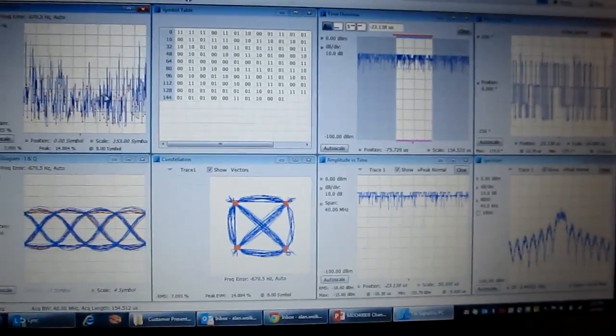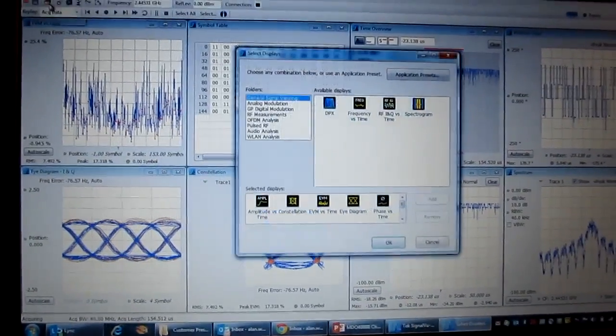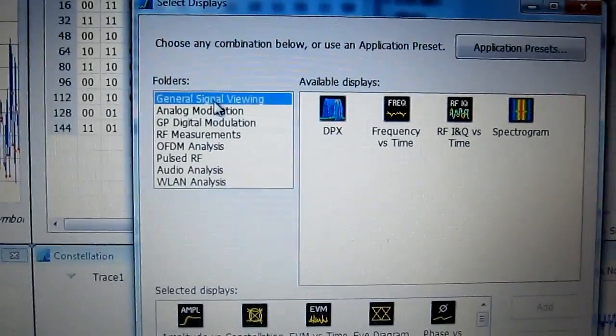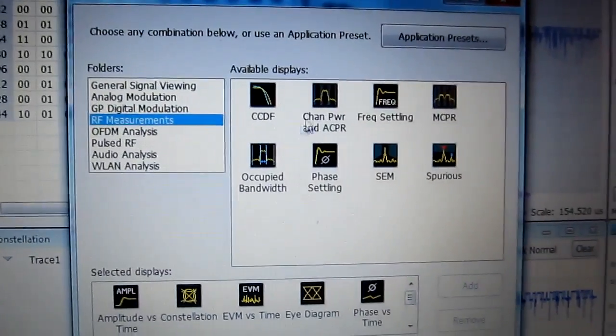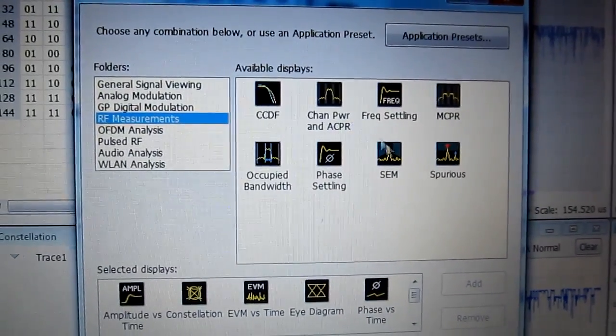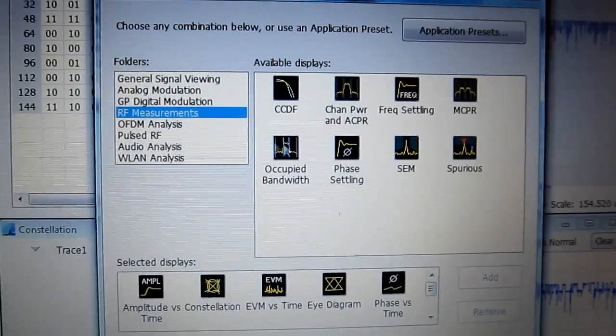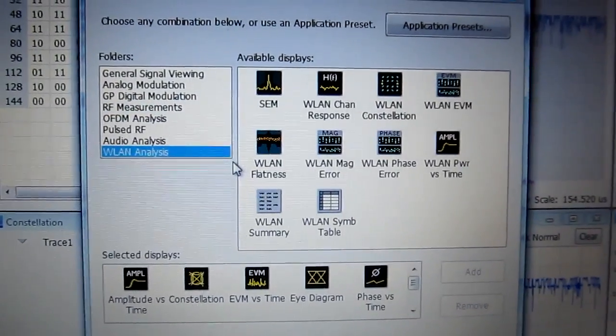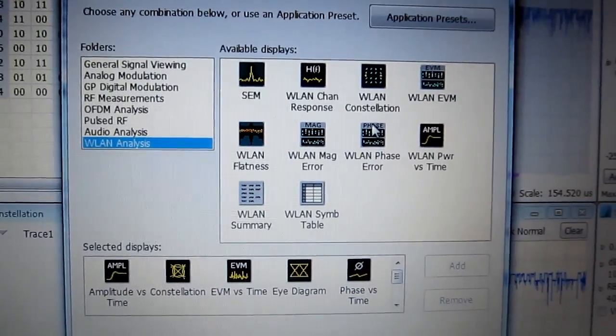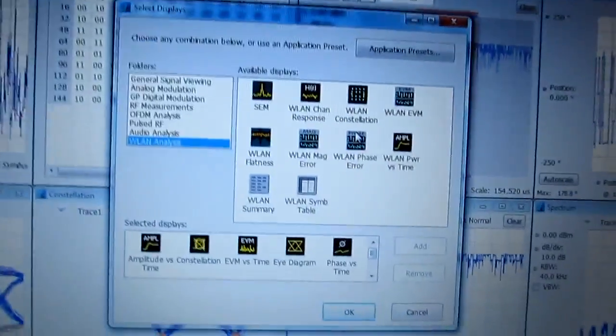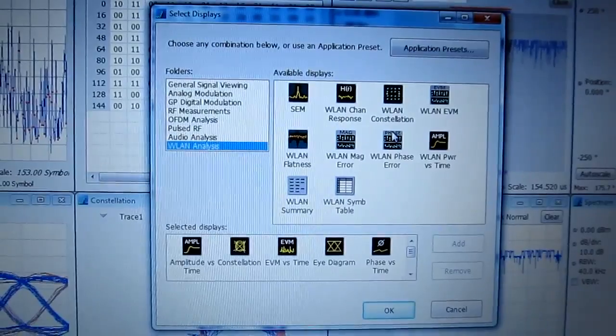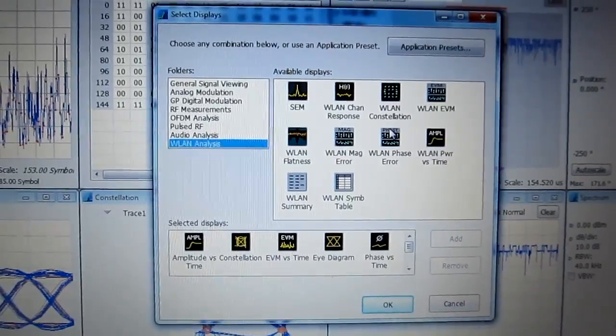So, you know, in my mind, the ability to bring in the full capability of vector signal analysis from general purpose analog and digital modulation, RF measurements, channel power, ACPR, spectrum emission mask, things like that, to more complex analysis like even wireless LAN analysis. We can do all of that now using the spectrum analyzer in the MDO as the source for all of the RF signals. So it really adds a whole other dimension or several dimensions of analysis capability beyond what the MDO brings in the first place by itself.